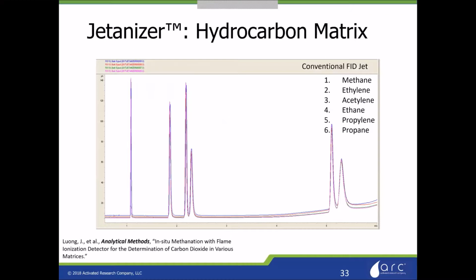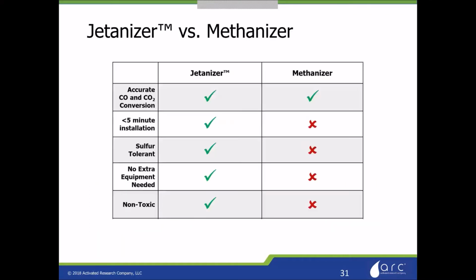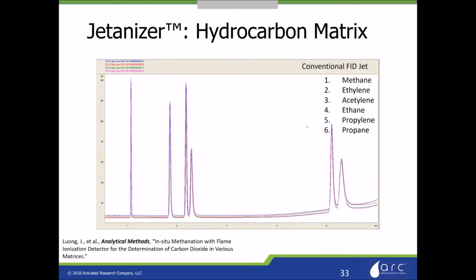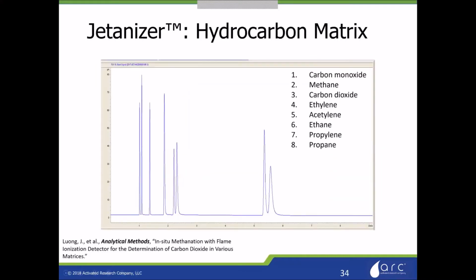If you now look at a conventional FID jet, this is some work done by Jim Luong at Dow Chemical. There's an analytical chemistry article written by Jim Luong about these products, and in this case he's looking at CO and CO2. This is with the conventional jet. And then with the Jetanizer, you can see the additional peaks for carbon monoxide and carbon dioxide, and you can see very good peak shape. There is some broadening, and that's mostly from the column for the propylene and propane.